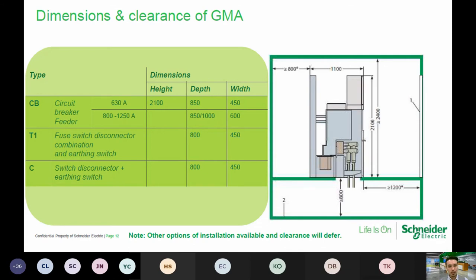I think one key point to highlight is that when we put the rear to the wall itself, we still need to give some spacing, about 100 mm, once it's on the wall. And we also need to take note that especially for the recent SS code, SS 638, it talks about the minimum clearance at the front being about 700 mm around the panel, right? Also take note of the height as well. So the height here is 2100 mm. All right, so you need some top clearance as well, around 300 mm.